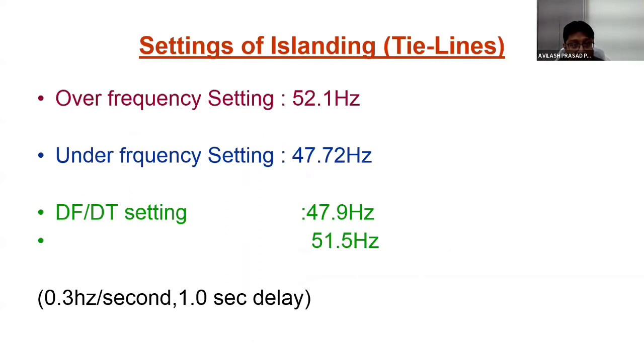Settings of the islanding tie lines: over frequency setting is 52.1 Hertz. Under frequency setting is 47.72 Hertz. df by dt setting is 47.9 Hertz and 51.5 Hertz, 0.3 Hertz per second and 1 second delay.